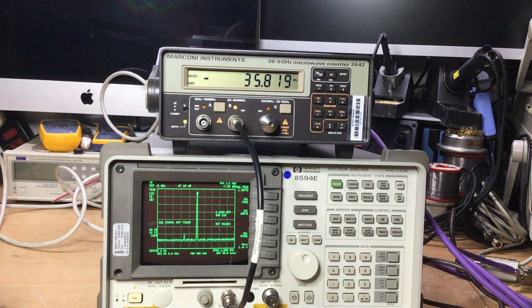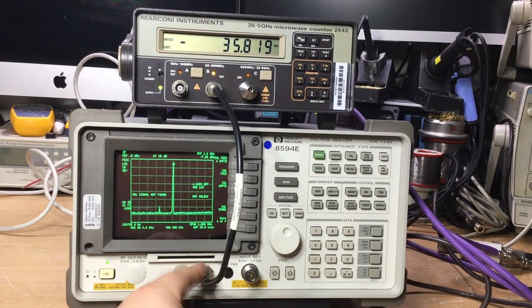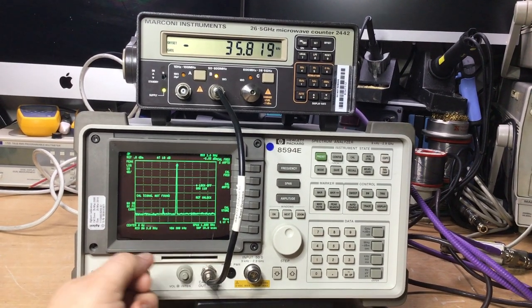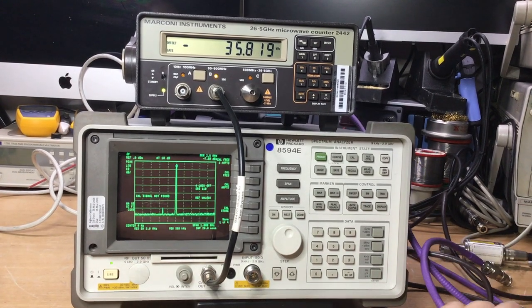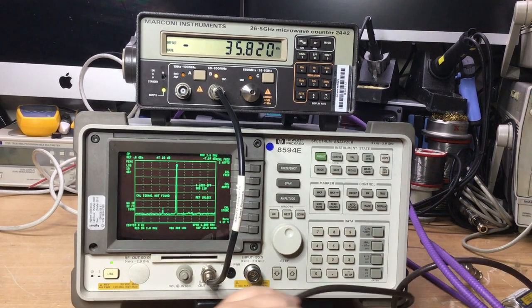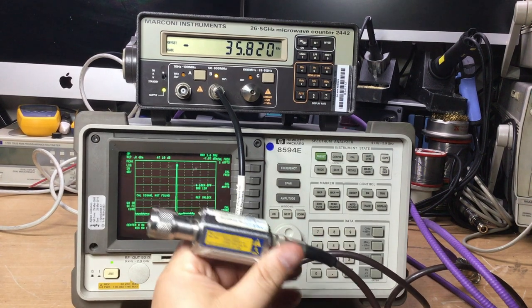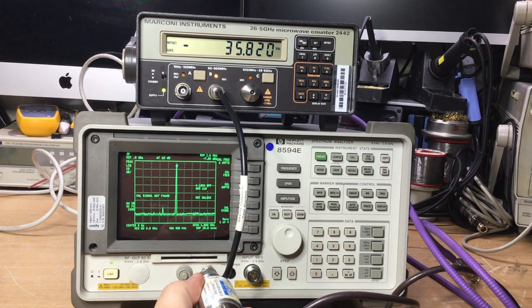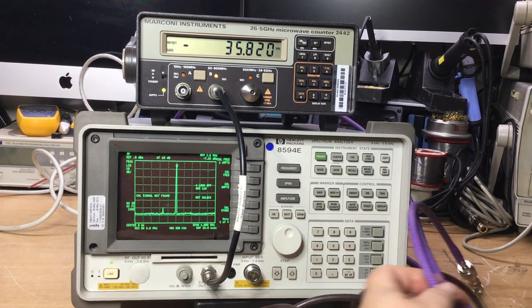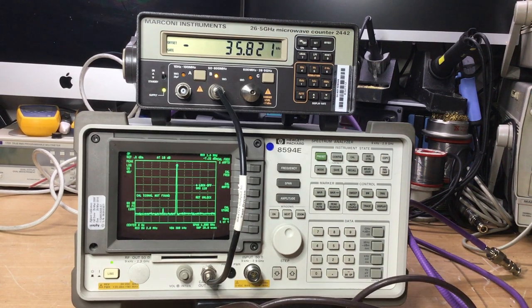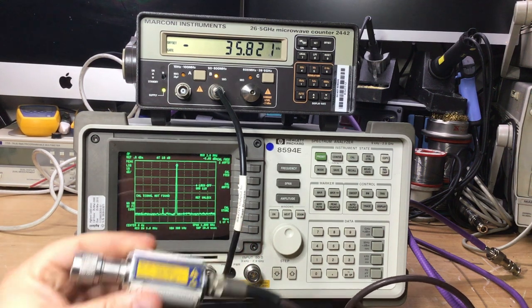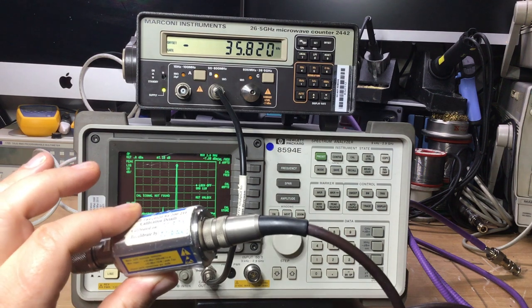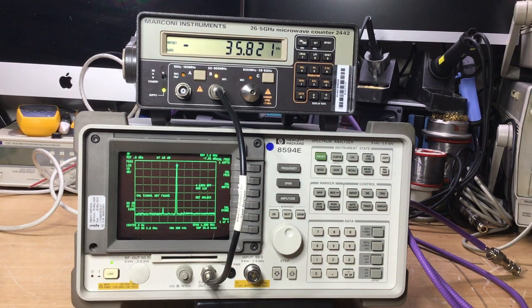So now that I know it's off frequency by 35 kilohertz, I can make a mental note of that, and now we'll then go on to the Marconi RF power meter. Now using an RF power probe, we'll calibrate the power probe and then we'll connect it directly here, so it's measuring the RF straight from the BNC on the front of the spectrum analyzer directly at that port. And that way then it gives us a truly accurate measurement, because it's an RF power probe, and that's the RF power probe that we're going to be using. And that measures power directly at the socket, whereas RF cables and such like that are lossy, so the loss is obviously great in the cable. So this is highly accurate. I'm talking a 0.1 dB accuracy. So it's extremely important to calibration that we use things like these probes in order to measure directly at the port.